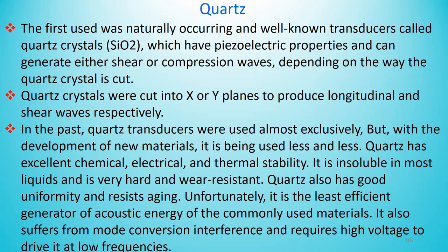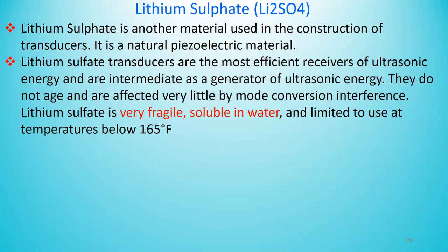In the past, quartz transducers were used almost exclusively, but with the development of new materials, it is used less and less. Quartz has excellent chemical, electrical, and thermal stability. It is insoluble in most liquids and is very hard and wear-resistant. Quartz also has good uniformity and resists aging. Unfortunately, it is the least efficient generator of acoustic energy of the commonly used materials. It also suffers from mode conversion interference and requires high voltage to drive it at low frequencies.